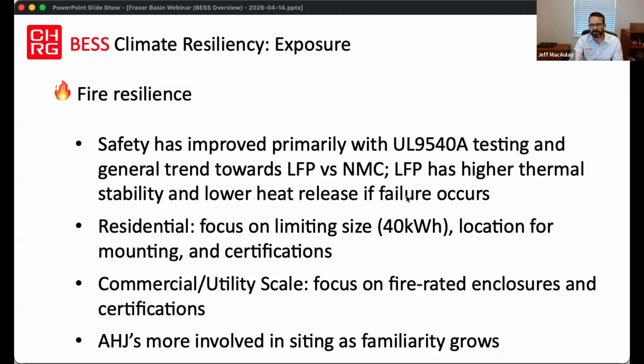Apologies for all the text on the slide, but I'll cover these couple of points. One thing that's happened in the last 10 years is a safety standard called 9540, a UL standard now required in Canada for all battery systems to be tested to. Residential scale products are tested as a type spec at the factory, so every battery shipped is certified, whereas most larger scale applications are field certified. Either way, they have to go through this testing standard. One test added to the overall standard is 9540A, a fire propagation standard.